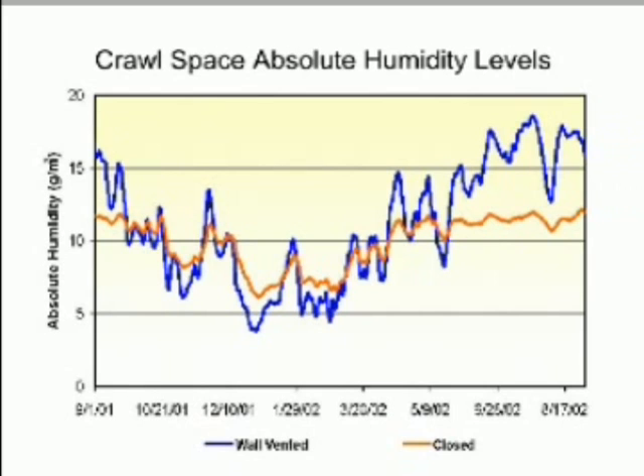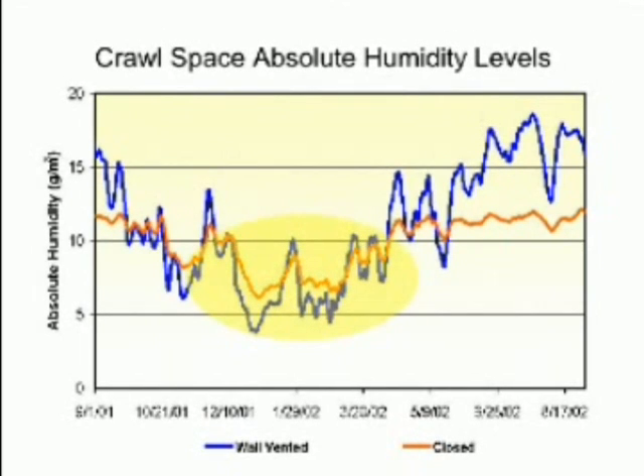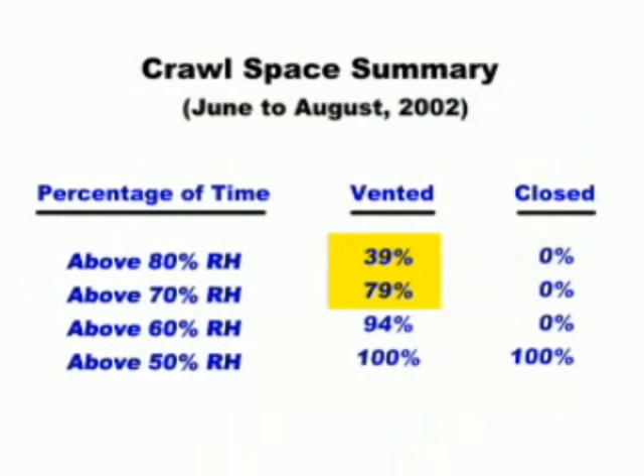This next graph shows what absolute humidity conditions were for an entire year in the field test. Absolute humidity is a measurement of how much water vapor is in the air. This graph reveals that during the winter, both the wall-vented and closed crawlspaces reached their driest conditions, and they ended up performing about equally well. Since winter results in drying conditions for both groups, crawlspace moisture control efforts really need to focus on the wetting effect that hot, humid weather has on wall-vented crawlspaces.